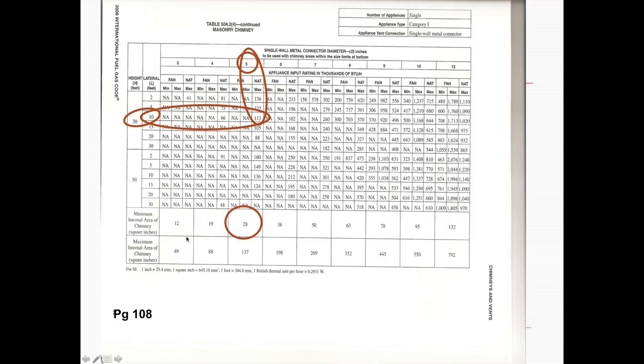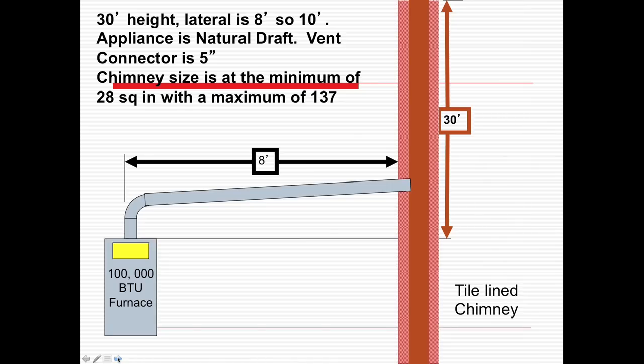Going down in this chart, the five-inch connector can go into a chimney with a minimum and maximum internal area. The minimum internal area is 28 square inches and the maximum internal area is 137 square inches. Our chimney is 28 square inches — that meets the minimum of 28 and is well under the maximum of 137. So this one will work.